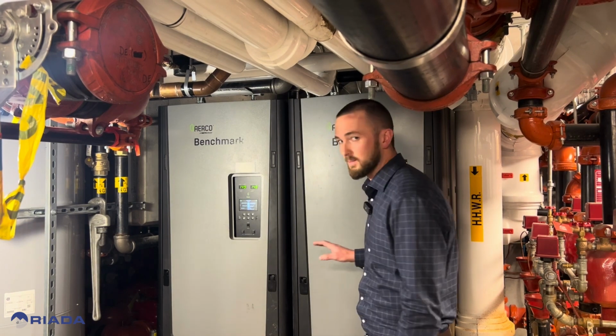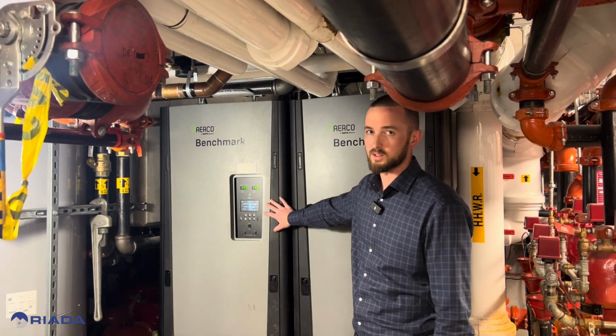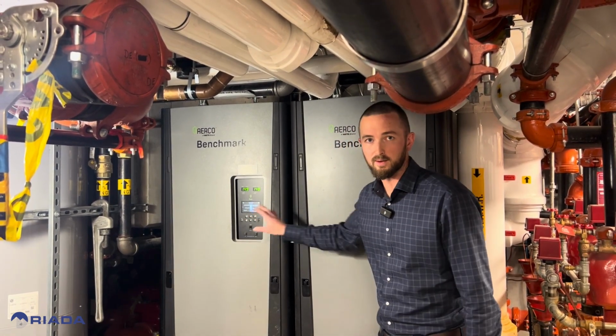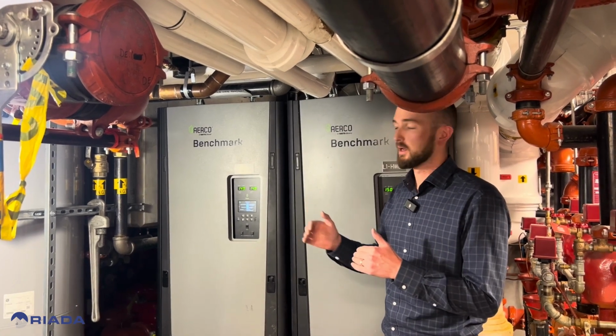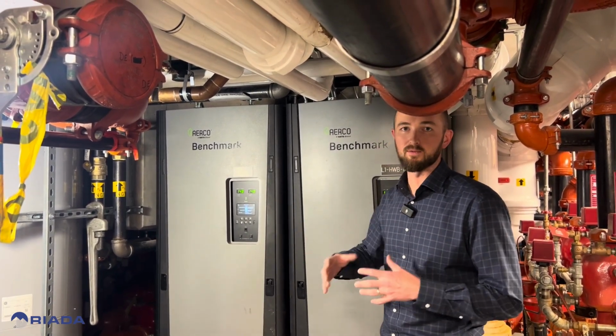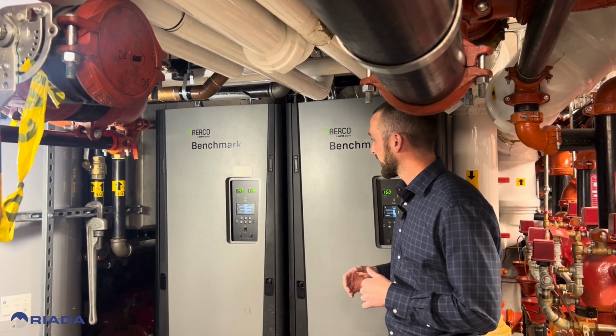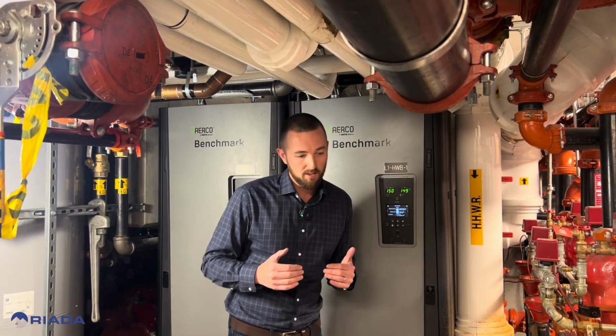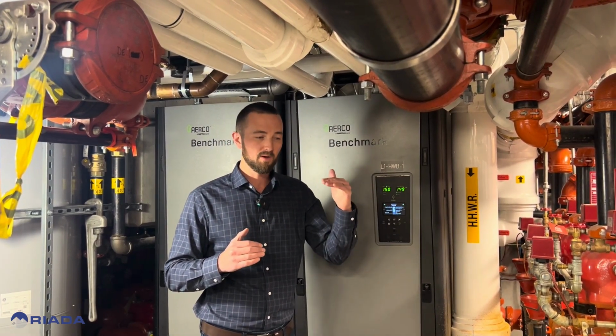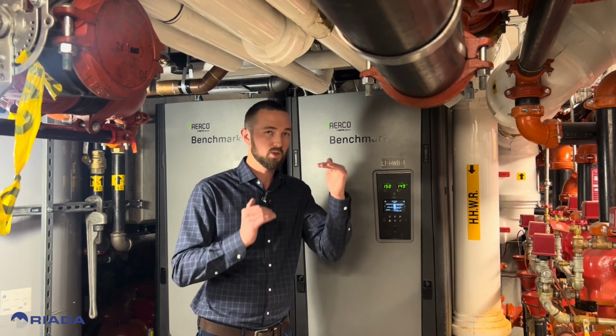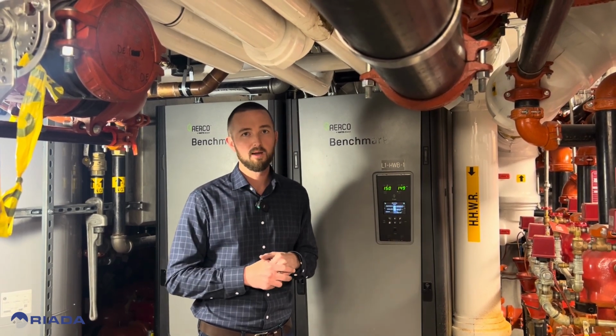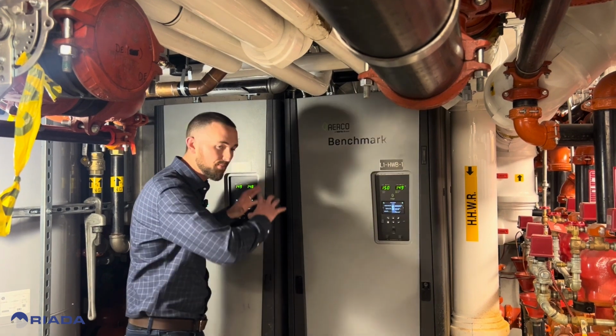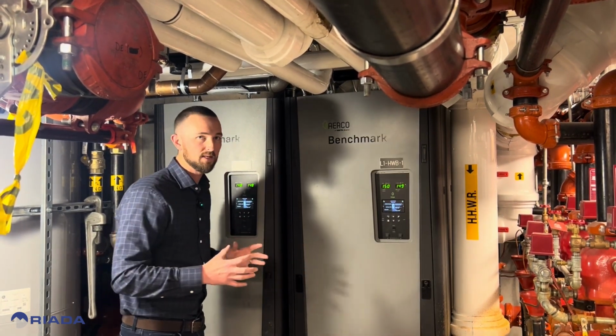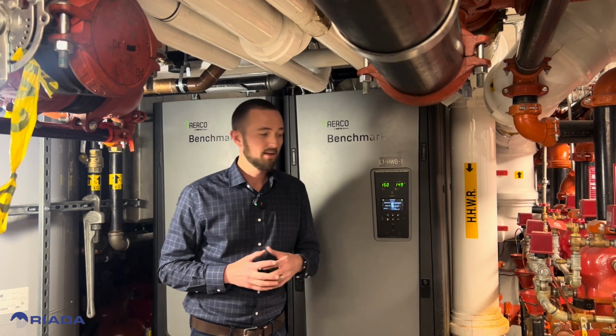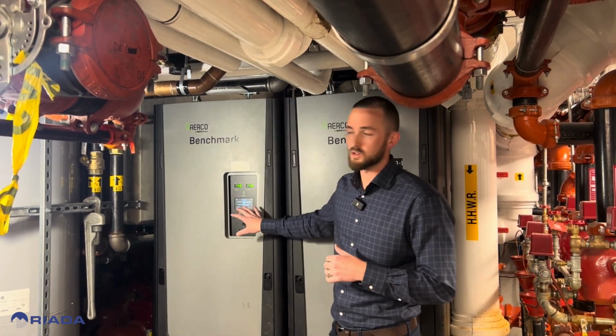Now, another item here is these advanced edge controllers. The edge controllers speak to one another, and they will stage each boiler on by themselves without the need for a separate wall mount controller. What these boilers will do is bring on one boiler to about 50%, and before continuing, if they need to ramp up further, the second boiler will come on and they'll both drop to about 25% and keep going up from there. This ensures that your maximum total heat exchanger surface area is utilized in your design. And this is handled and controlled by the edge controller.